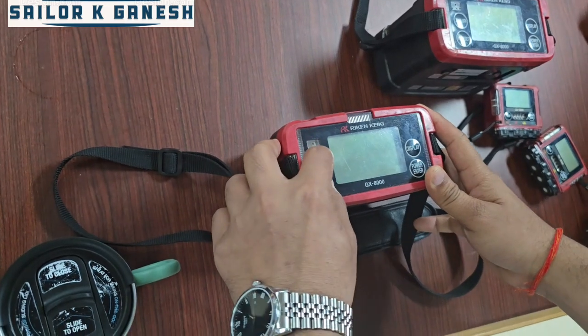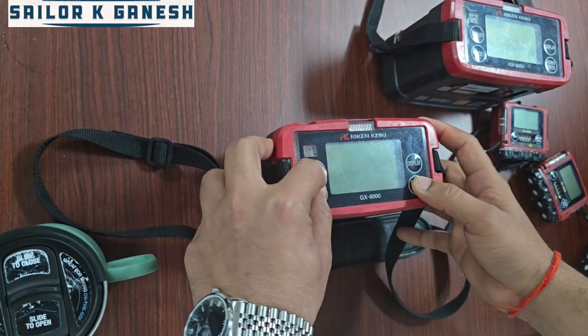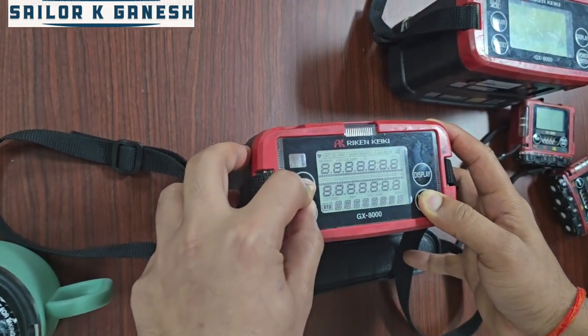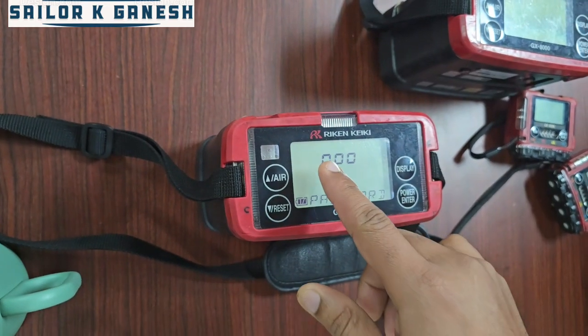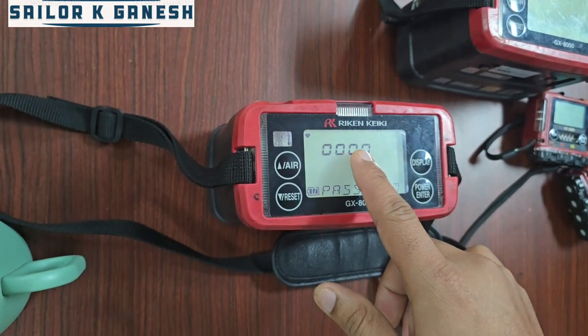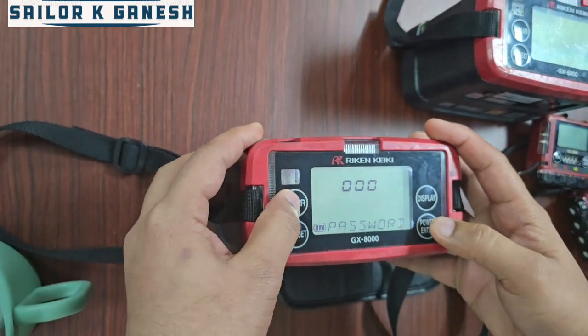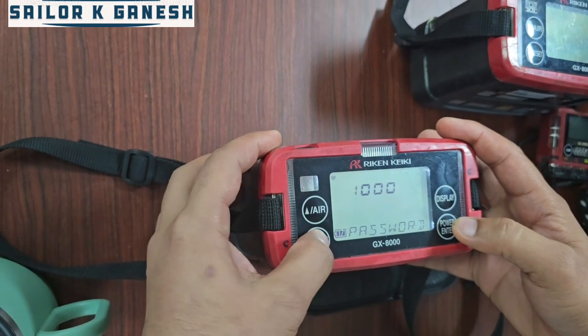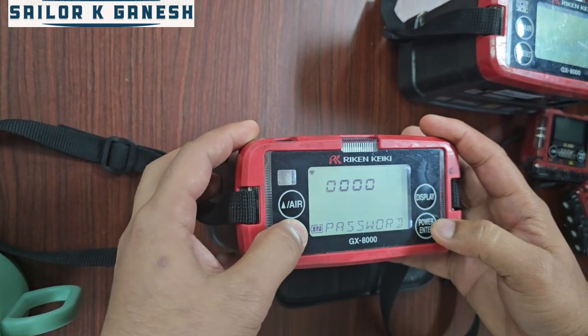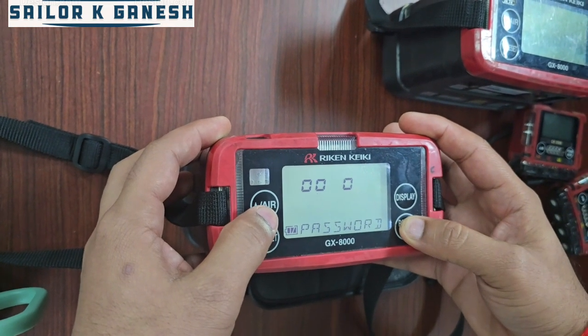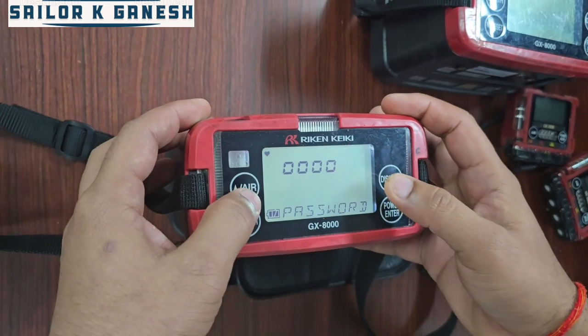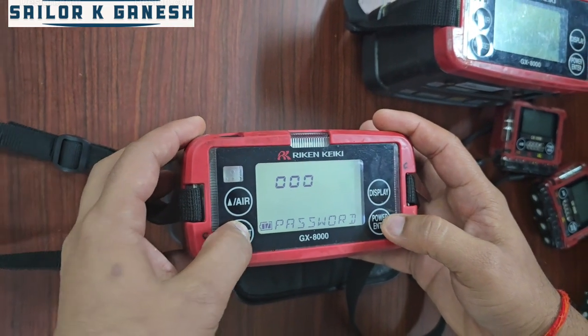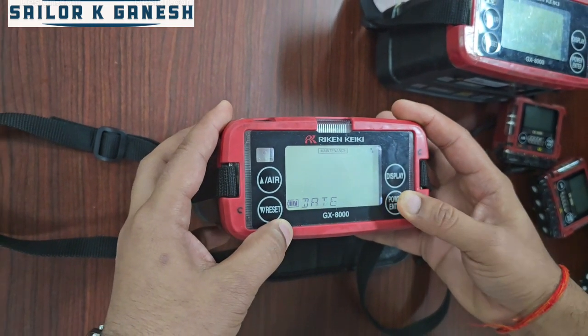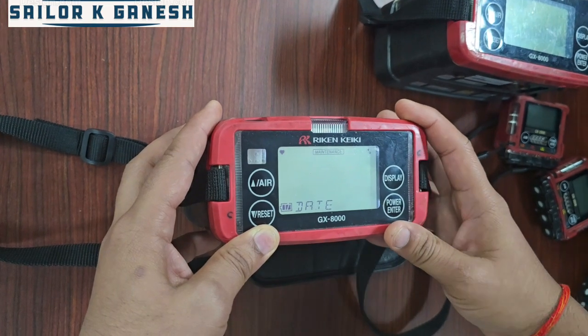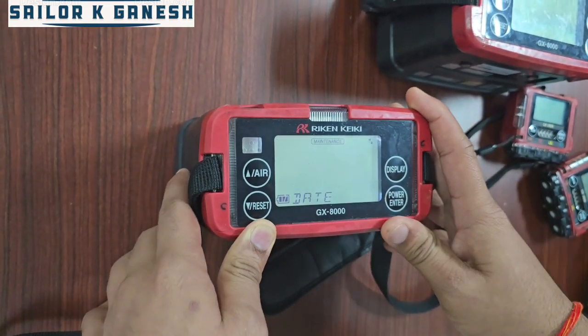Together with air, reset and power button, we have to press all these three together, and then it will go into the calibration mode. We have a password, 00018. So we go one by one. This zero, already zero is there. Next, and then next. Then here we have to go for 8. Okay, this is the password. Then go inside. Now it is in the calibration mode, also the settings mode.